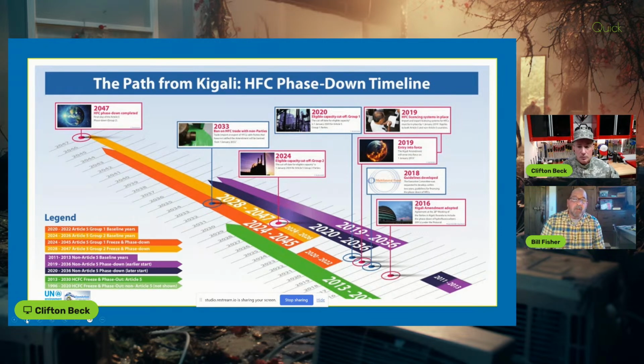And there are some practices we're going to have to change. We have to make sure the equipment's A2L qualified, and that our building codes will accept it, because some have not passed that yet. We just had the EPA approve the technology transition rule, which will remove our high GWP refrigerants, HFC refrigerants like R410A. For our sector, residential split systems, that's January of 2025 - there will no longer be R410A residential split systems after January 1st of 2025.